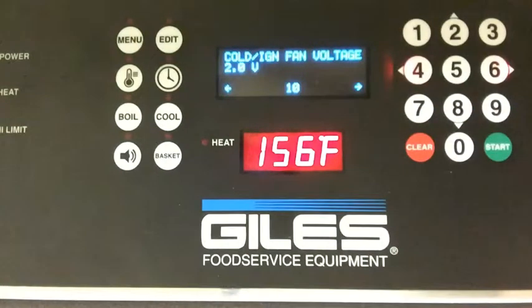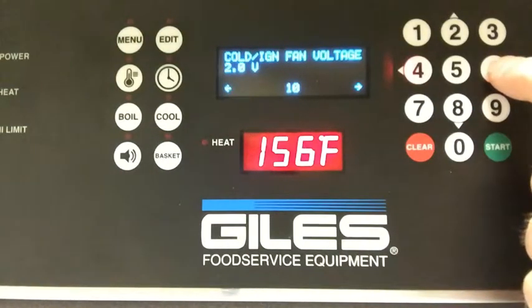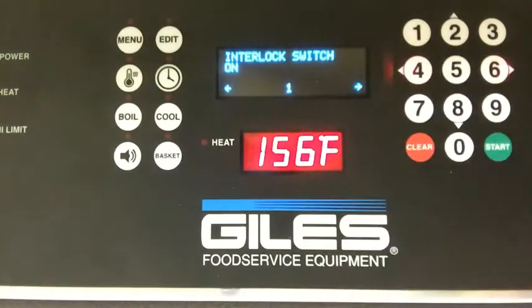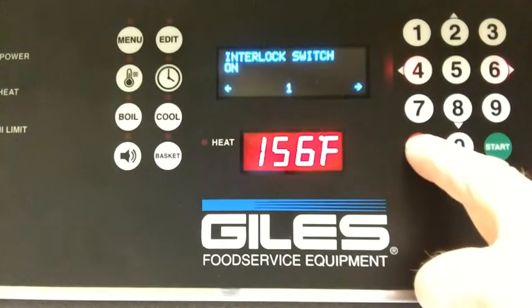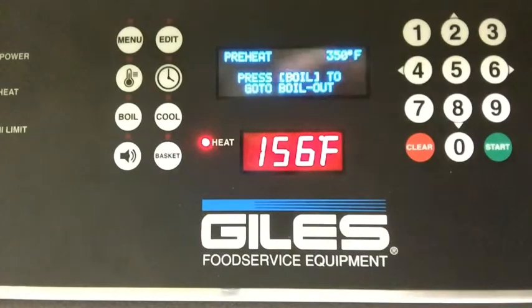Cold ignition fan voltage, gas machine, nothing to do with this machine. High fire, nothing to do with this machine. Low fire, nothing with this machine. And then we're back to our interlock switch. We'll press clear, and we're done with those settings.